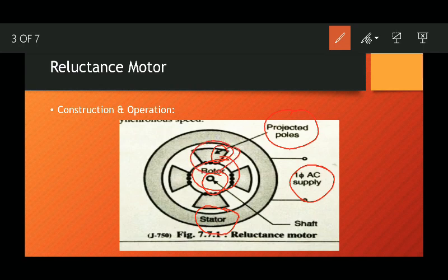When stator winding is switched on, a revolving field is established revolving at NS, where NS is synchronous speed. Due to the presence of squirrel cage, the motor starts as an induction motor and reaches a speed very near to synchronous speed.